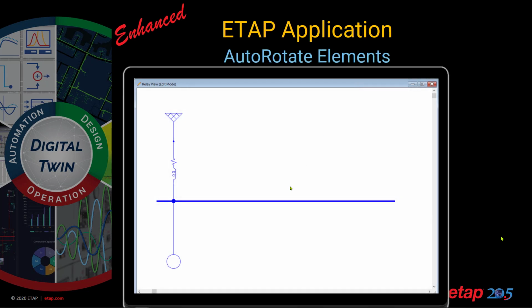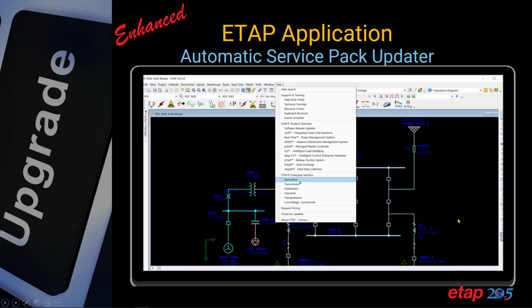Another very neat application is Auto Rotate. It lets you build the one-line diagram as usual, but as you move components above or below the bus, the program automatically and intelligently rotates them, making it much quicker to clean up and lay out the diagram. This works with sources and loads, but also with relays—you can move the relay back and forth and see the CT change its mirror position automatically based on where the relay is located.